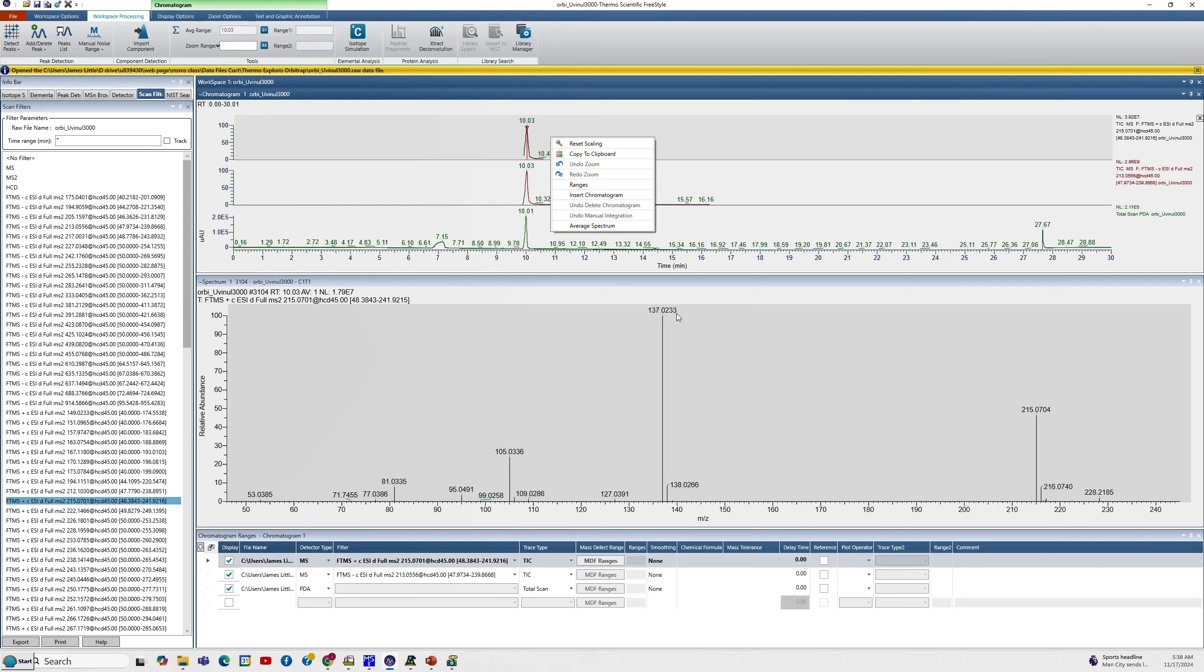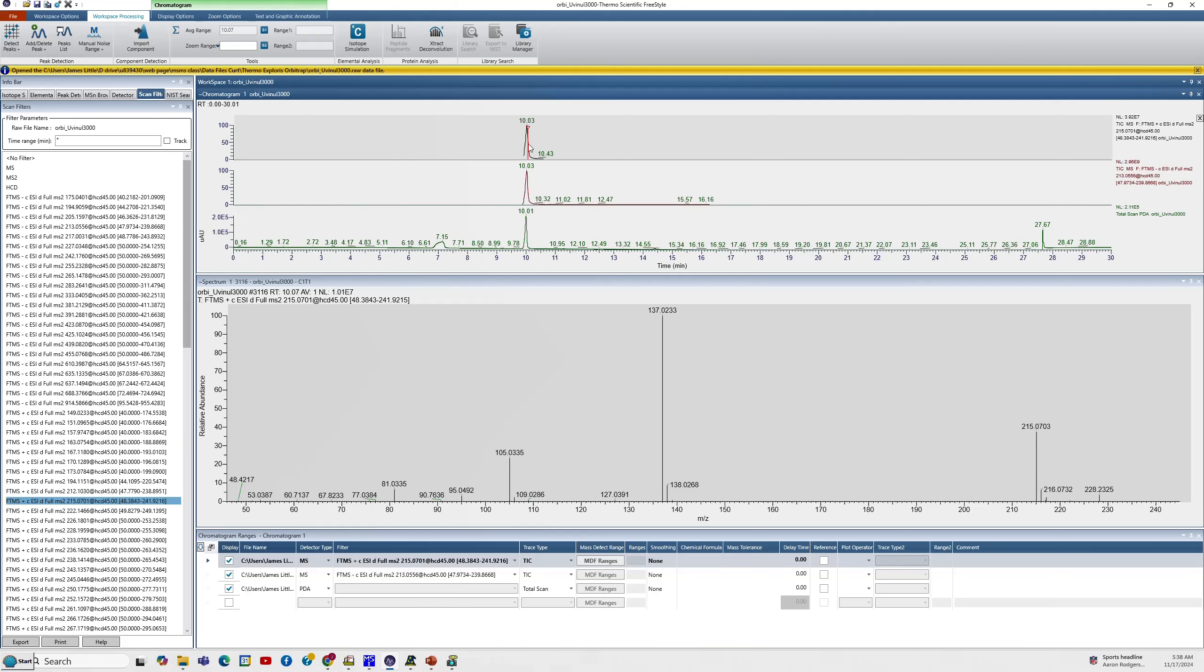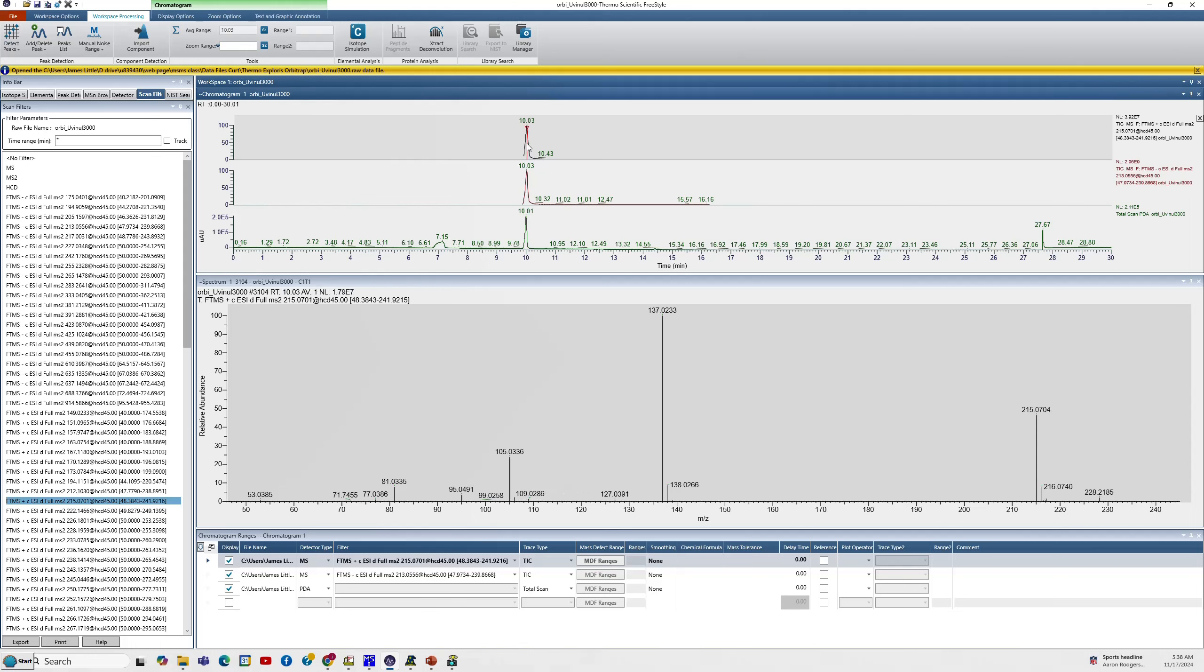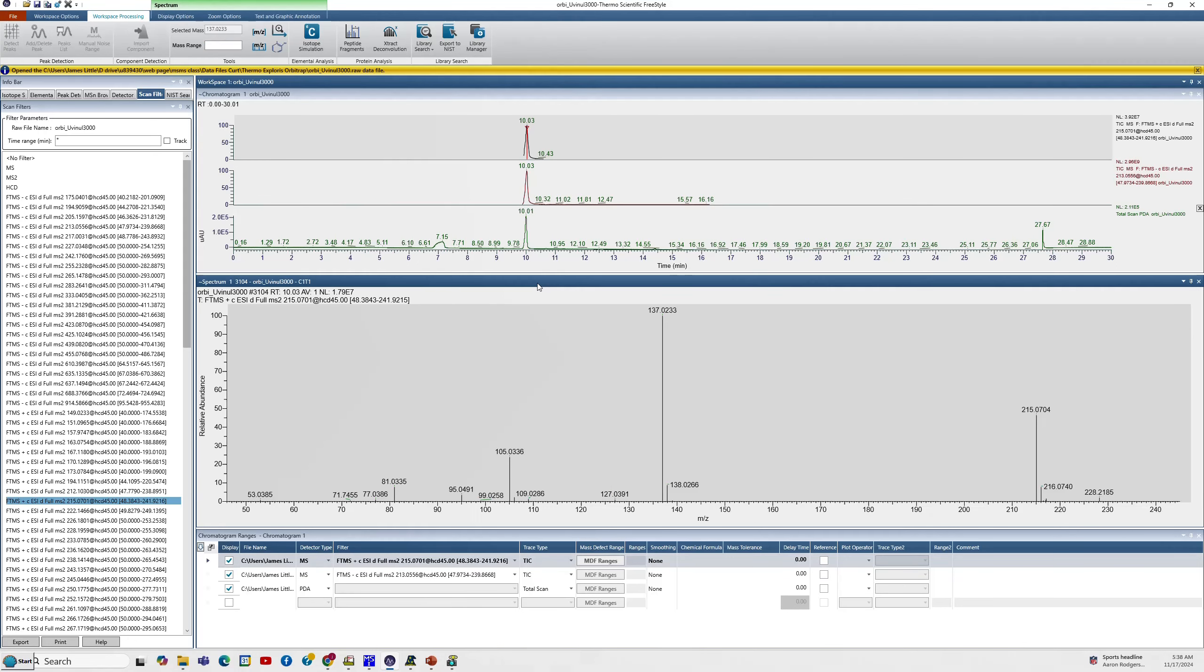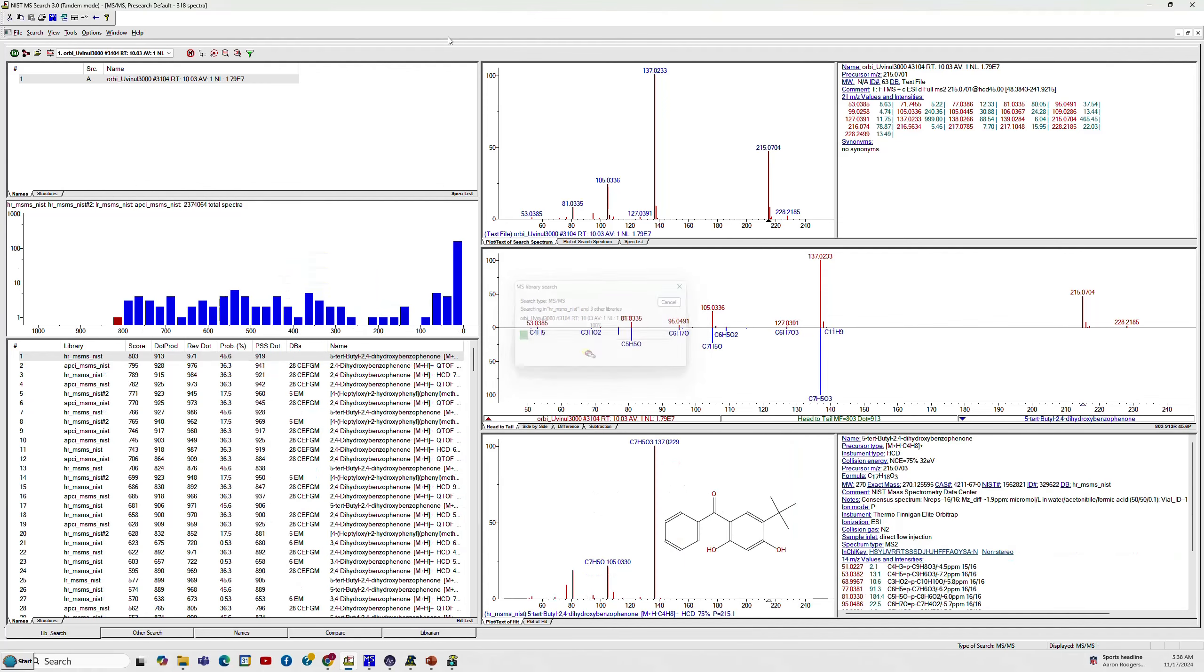So there is an option to average the spectrum but if you do that you'll lose the significant figures that show up within the software here when they're transferred to the NIST search. So it's best just to click on it different places. I'm just clicking different places on the positive ion to see if the spectrum is reproducible. So I'll just pick one spot by left clicking on the top to get the spectrum below. So we have it shown here and we'll have to select this box so I click on the title bar for it and that allows you to see the export to NIST box at the top here so you can send it to the NIST. If the program is not already open, the NIST program is already open, it will open it but I've already got it open so it'll go directly there and search.